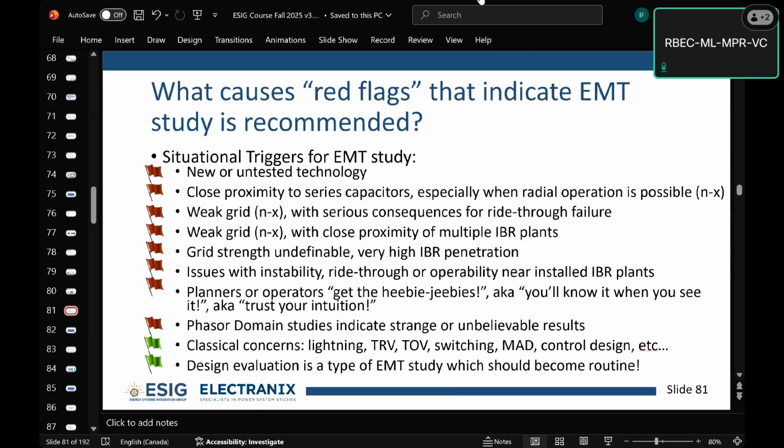And then that study's basically done and you're into it for a week of work or something. How often does that happen? That does not happen very often. But this is a lesson: what is really important is that if those models are good, if they've been checked and validated against actual system models, the studies go so much better. If you start with bad models, either you don't see what you're supposed to, or the models are not behaving properly, or you're going back and forth, or you find out that it wasn't the as-lefts or whatever. So that's a big variable on cost and schedule and actually study effectiveness.